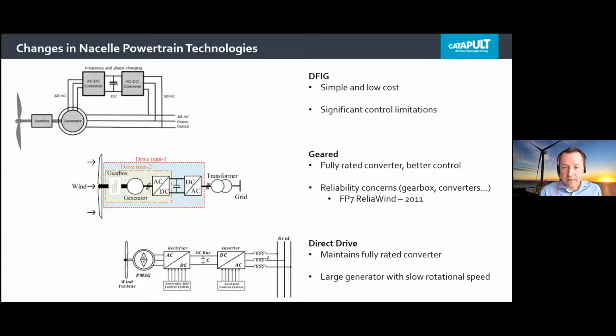Direct drive still maintains the fully rated converter, but now you've effectively removed the gearbox. So you're dependent on a very large generator with a very slow rotational speed. This means the generator challenges are different, but the turbines are much bigger, so there are certain opportunities afforded in terms of where you put the equipment.